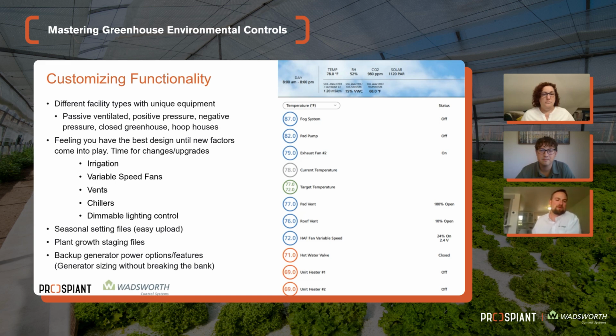So what we do is we see a lot of load shedding in the control system itself, and we can program any individual piece of equipment not to turn on during a power outage event or when we're running the backup generator. The other nice thing about this is we have alarms for everything. You would know should you lose power, what's going on.